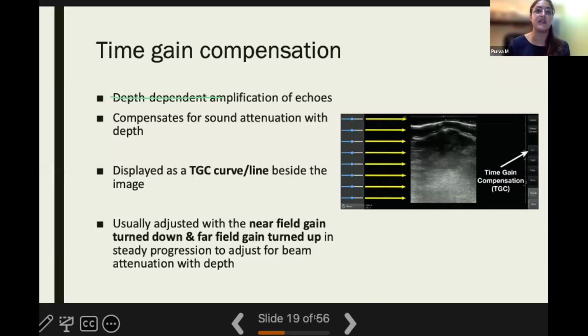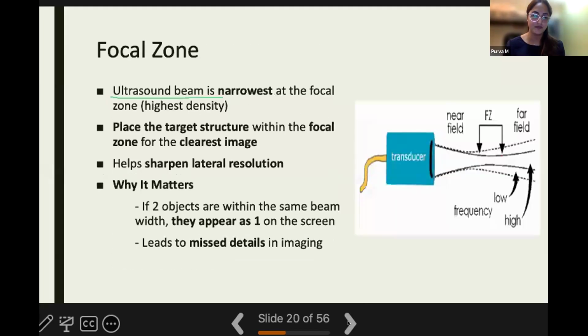Now, time gain compensation and gain both require frequent readjustments because different tissues will attenuate sound differently, and we are going to constantly move the probe. Once you have your final image in place, you probably don't have to move your gain settings at all, and you use the fixed gain settings to conduct your nerve block.